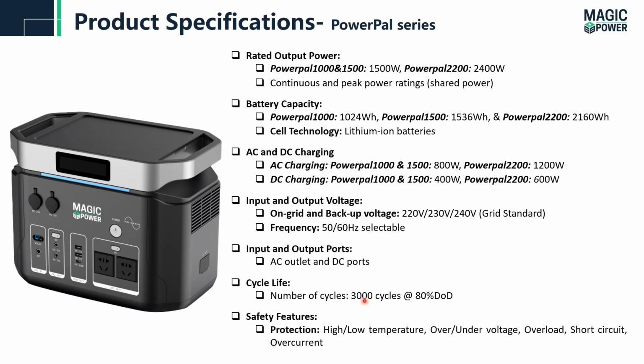Life cycle of the batteries: the number of life cycles is 3000, at 80% depth of discharge. Basically, one cycle we consider as charging from 0% to 100% and discharging from 100% to 0%. But in the case of 80%, it's charging from 20% to 100% and discharging from 100% to 20%. The safety features of the system include high and low temperature, over and under voltage, overload protection, and short circuit and overcurrent protections.